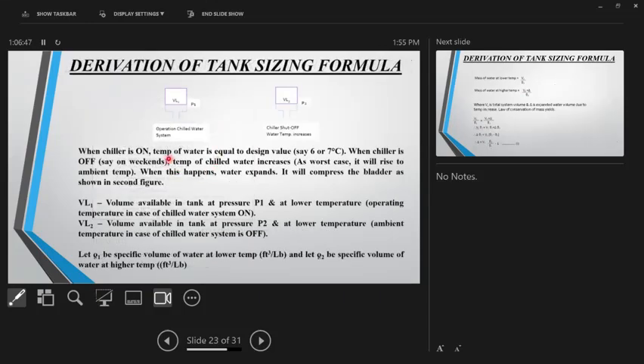So this is an attempt to derive that equation. These two are expansion tanks. This is when the chilled water system is running. Let's say it's your commercial building. So 6 to 7 degrees centigrade is usual for your chilled water system. For a data center, it could be higher. So when the system is operational, the temperature is, let's say, 6 degrees centigrade. And when this system is off, let's say on weekends, the chilled water temperature rises. And as we spoke, in the worst case, it will rise to ambient temperature. So this is the operational system, and this is when the chiller system is shut off.